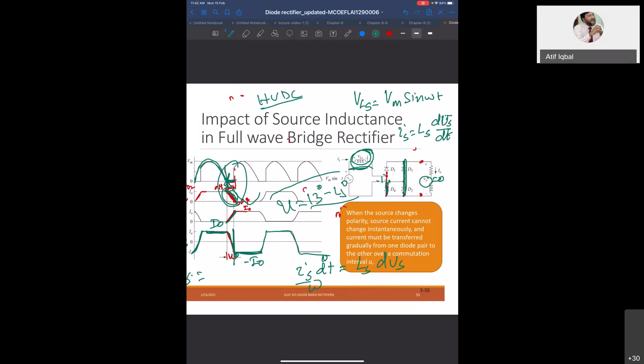The whole takeaway is that if you have an inductor in the source, which is there in practice, there will be an overall reduction in the output voltage, and you can calculate how much like this. In HVDC applications, high voltage DC transmission, you have very big converters, rectifiers, even about 2000 megawatt rating, and huge transformers of 500 to 600 kilovolt. There are big inductors, and they will have an impact due to the commutation overlap, and you can go even up to 13 to 15 degrees of commutation overlap. So this is important to take into account in the practical system.